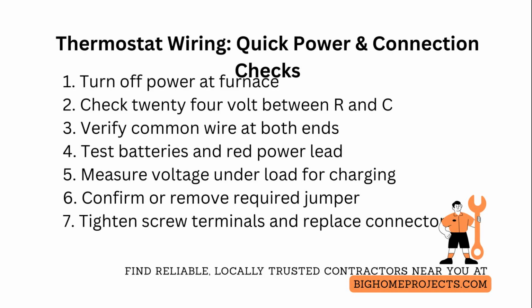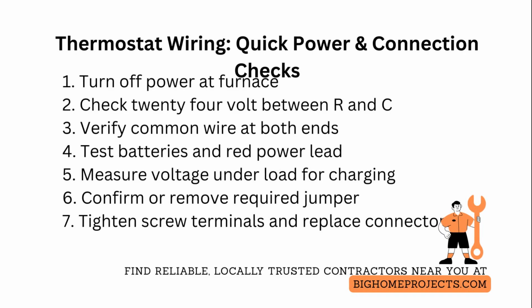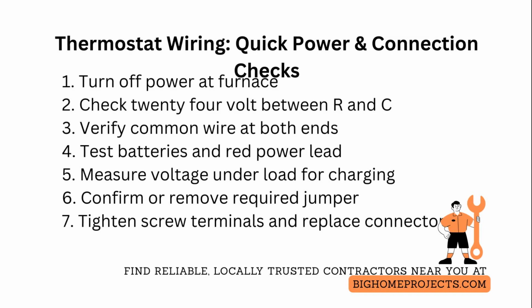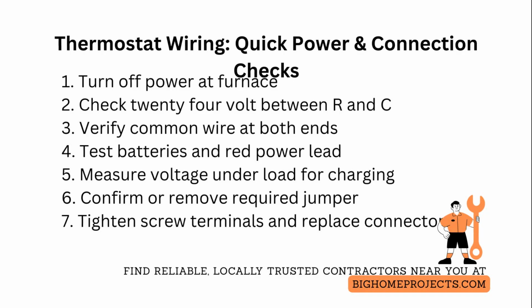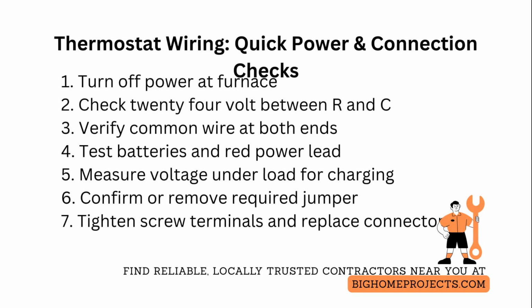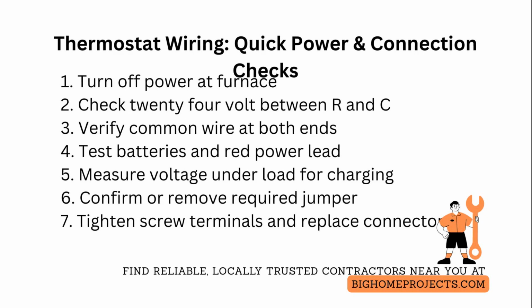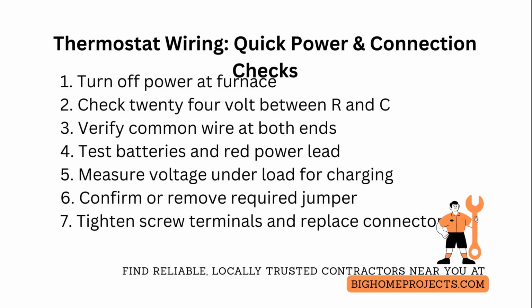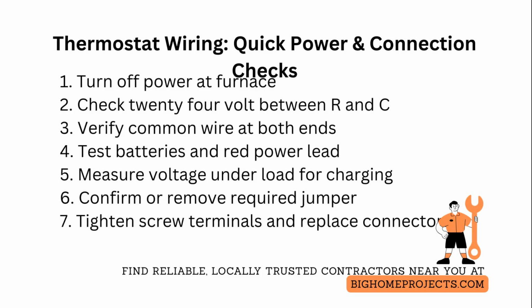If you have a battery-powered thermostat that still shows a blank screen, test batteries first, but also verify the red power lead is delivering voltage when batteries are removed, because some smart thermostats require both. For smart thermostats that need a power adapter or charge, check for a charging circuit fault by measuring voltage at the thermostat board pins while the thermostat is plugged in. A drop below 22 volt under load signals a weak transformer or long thin wire run causing voltage drop.